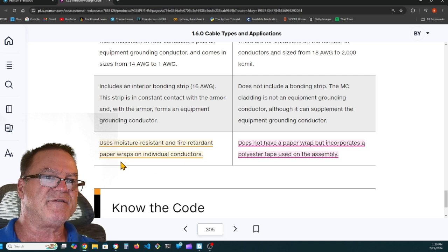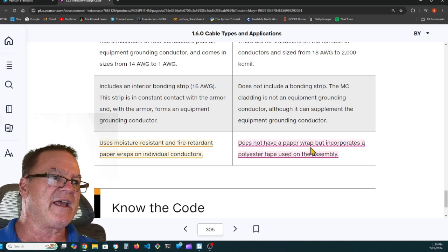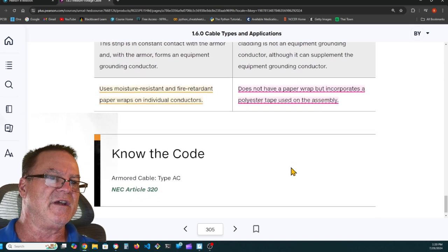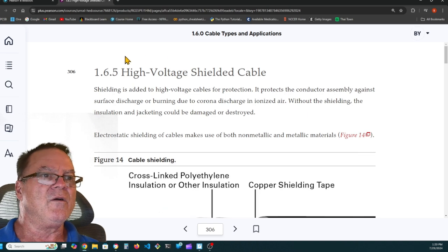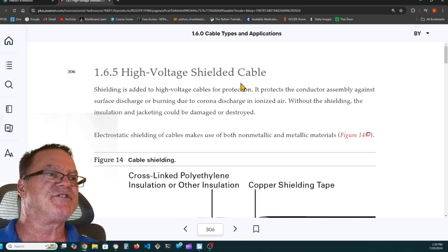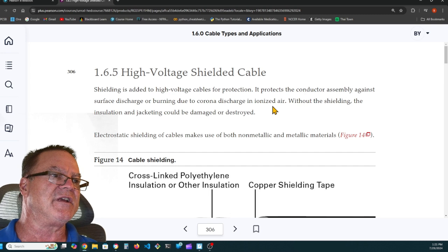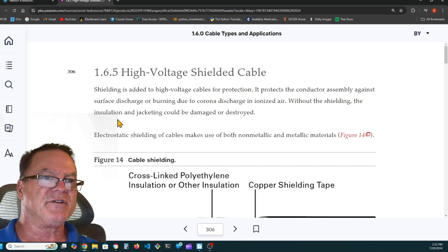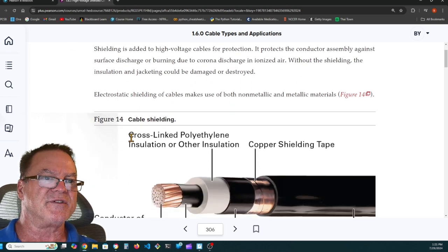Type AC uses moisture-resistant and fire-retardant paper wraps on individual conductors. Type MC cable does not have a paper wrap, but incorporates a polyester tape used on the assembly. Okay, 1.6.5, high voltage shielded cable. Shielding is added to high voltage cables for protection. It protects the conductor's assembly against surface discharge or burning due to corona discharge in ionized air. Without the shielding, the insulation and jacketing could be damaged or destroyed.